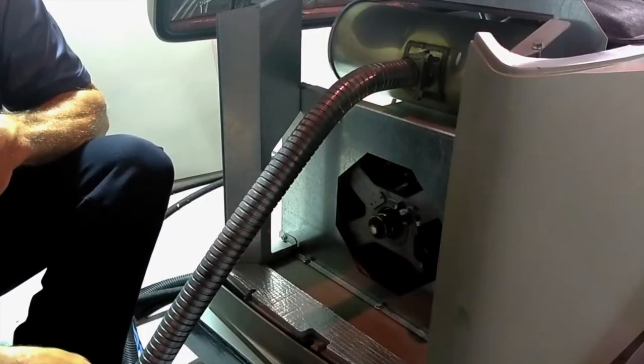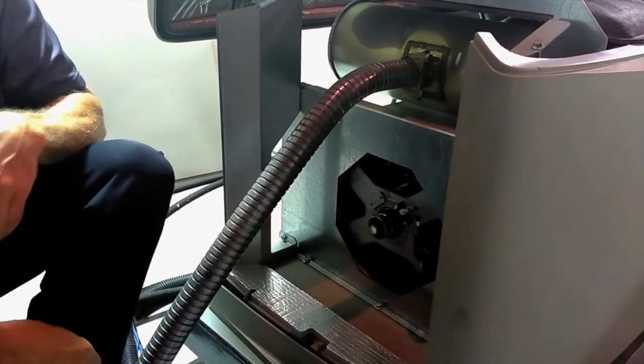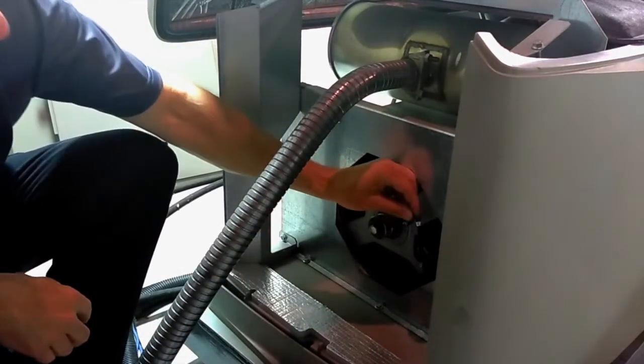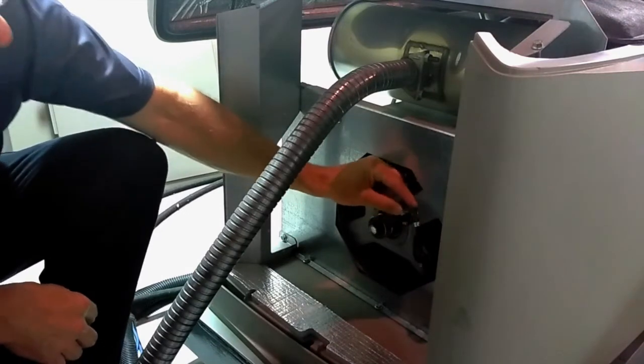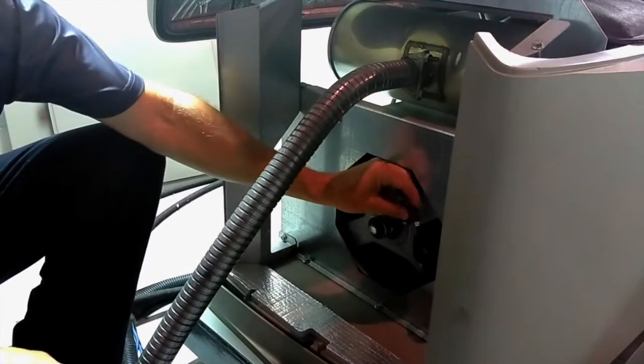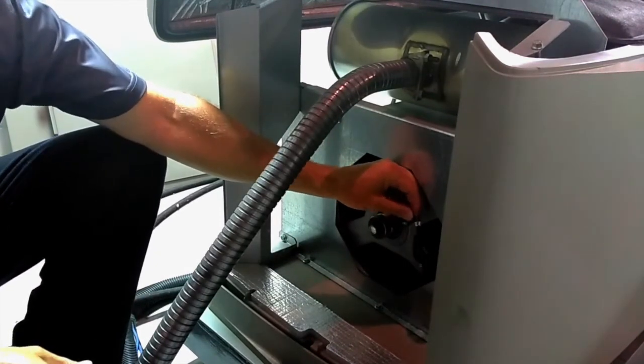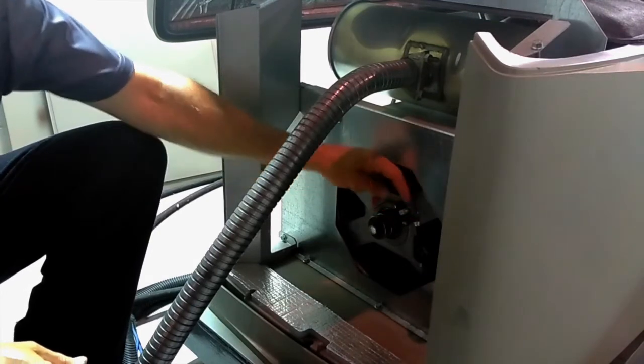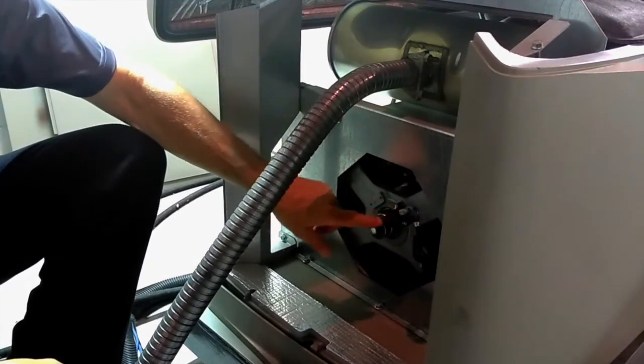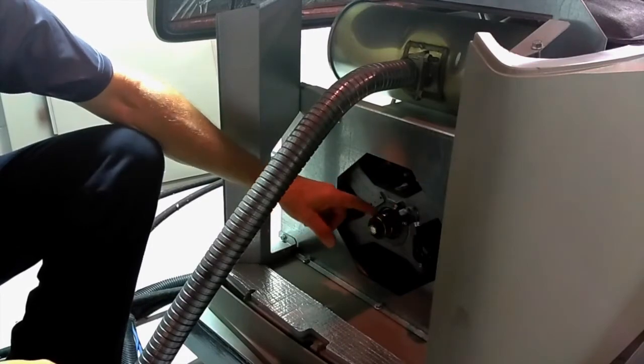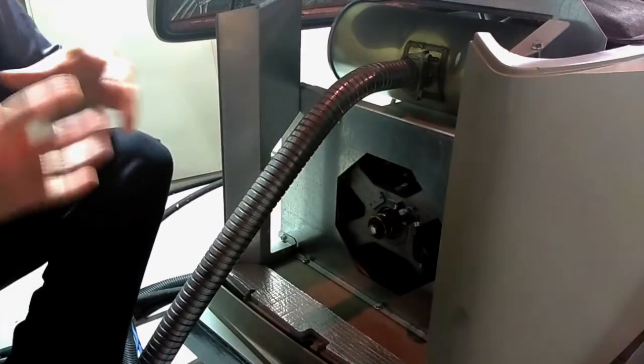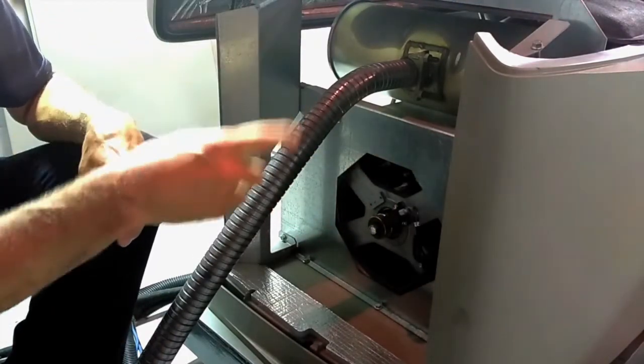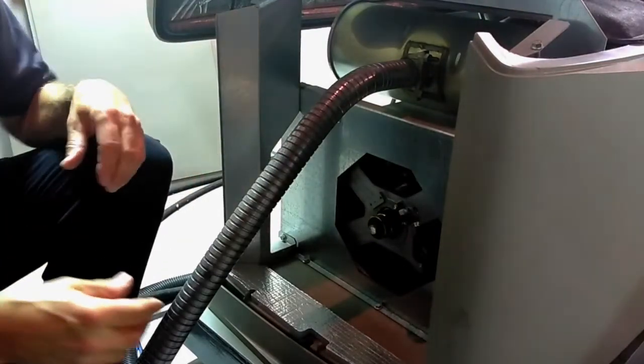So right now we have the harness, and now we're going to hook up to the brush block. On the brush block right now, you'll see we got a FP and FN that is coming from the controller P2 connector that is supplying us our voltage regulation for our field. So the voltage comes through, goes through the brushes to the slip rings, goes through the rotor and back, magnetizing the rotor, giving us a magnetic flux to cut our stator windings to give us our AC output.